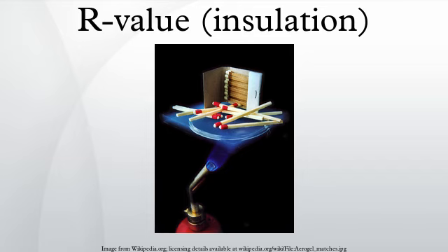Many manufacturers will rate the R value at the time of manufacture. Critics argue that a more fair assessment will be its settled value. The foam industry adopted the LTTR method, which rates the R value based on a 15-year weighted average. However, the LTTR effectively provides only an 8-year aged value, short in the scale of a building that may have a lifespan of 50 to 100 years.